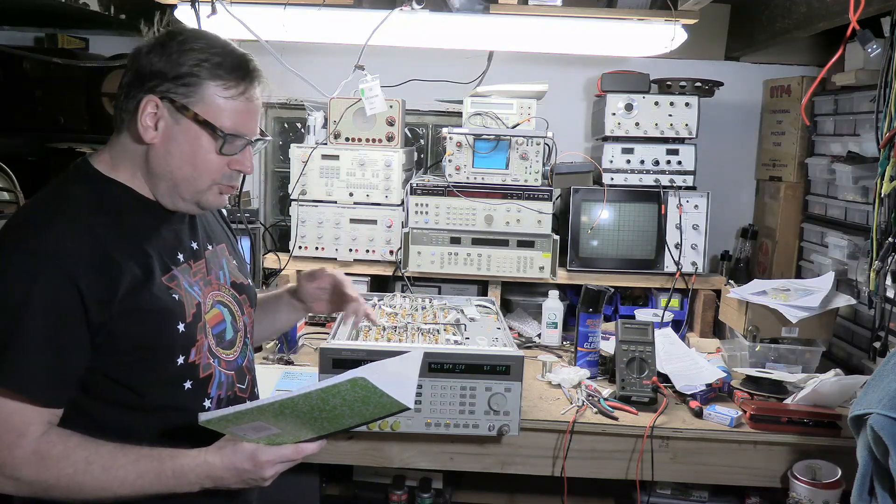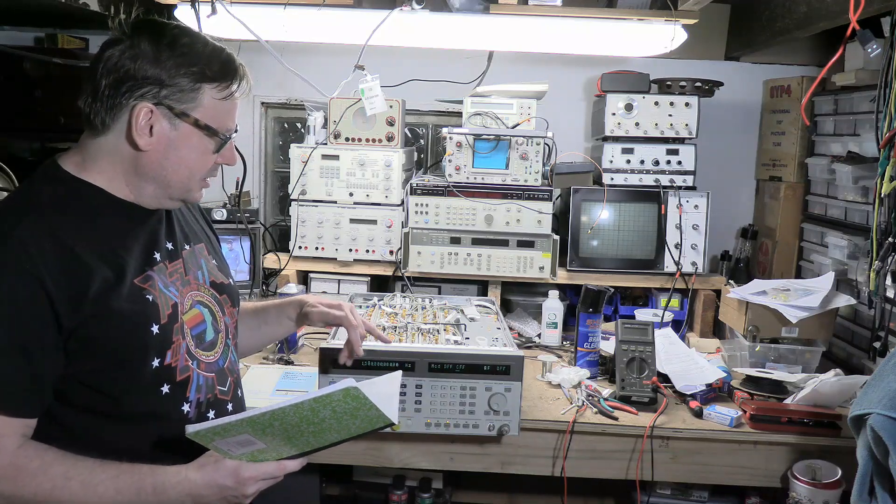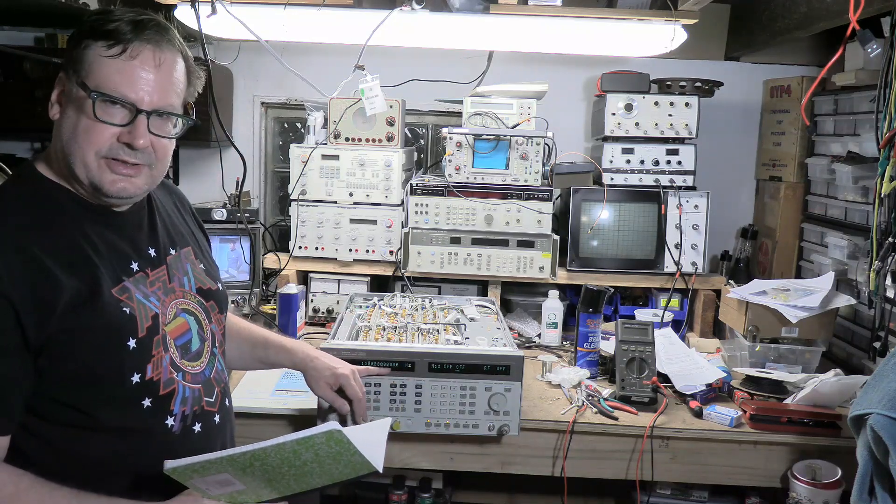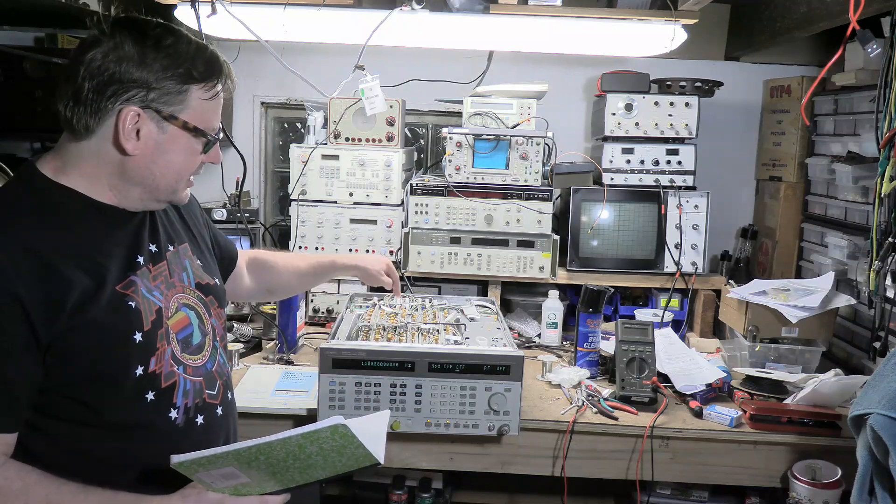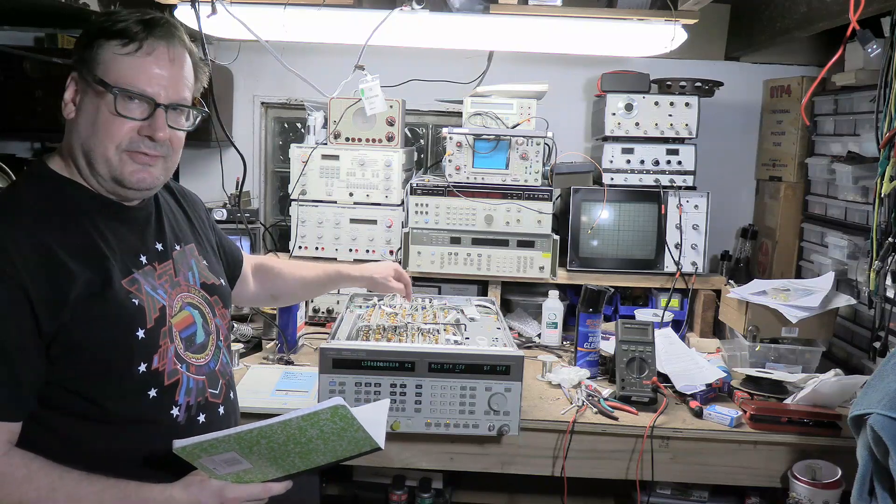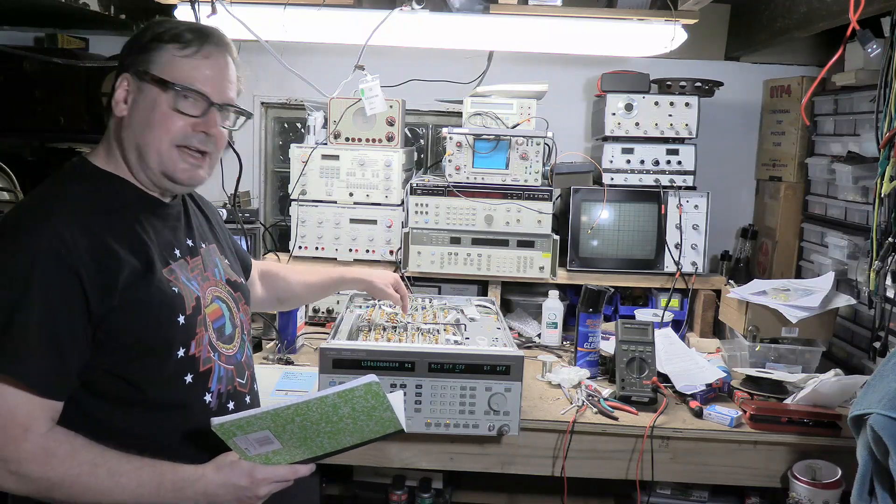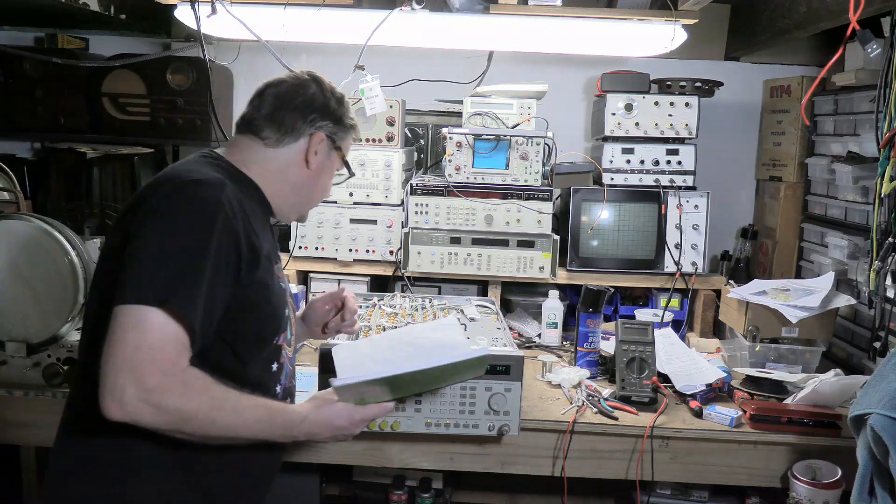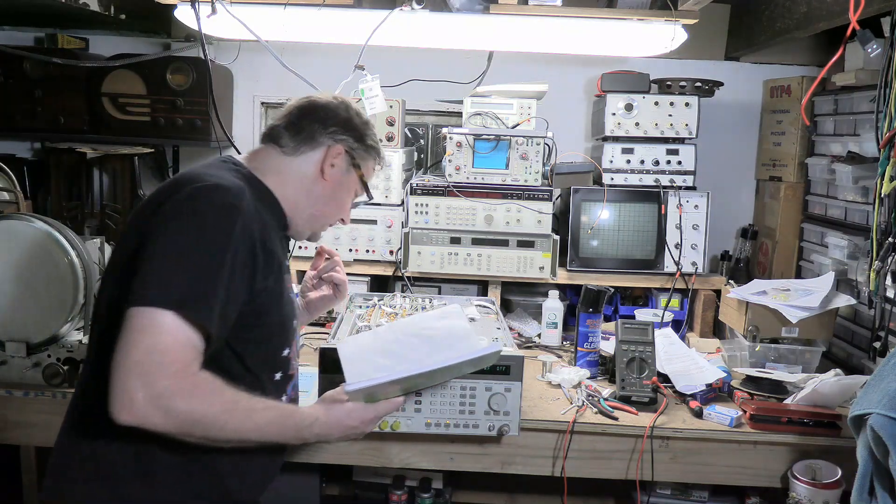When you run through an internal test, you're supposed to look at a reading on the display here and adjust a trimmer until you get the value handwritten on that module. Which is 1.708.